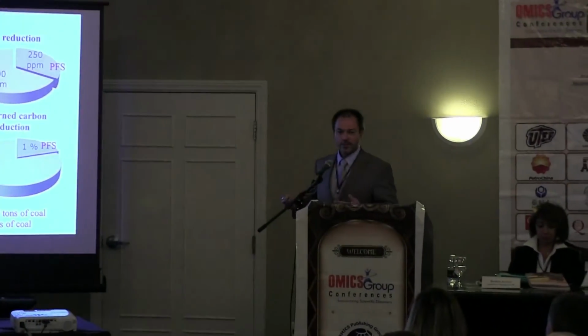In other words, 1 ton of fuel oil equivalent by caloricity can be replaced by 2 tons of coal. But at the same time, 1 ton of fuel oil equivalent by price is 20 tons of coal. So you can see the difference can be very big. For 1 ton of fuel oil replaced by coal, we have $200 of profit. And what is rather interesting, at the same time we have a reduction of NOx when the plasma torch is working, and unburned carbon is reduced 4 times in comparison with traditional technology.